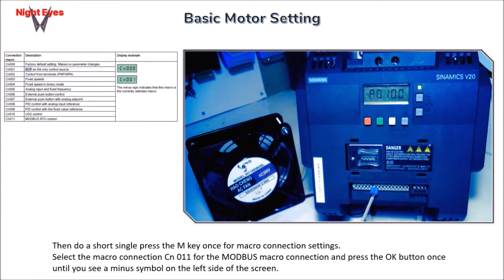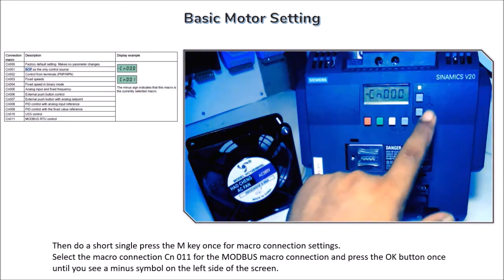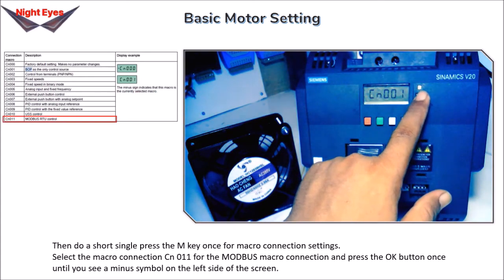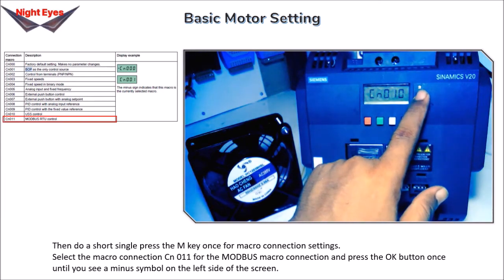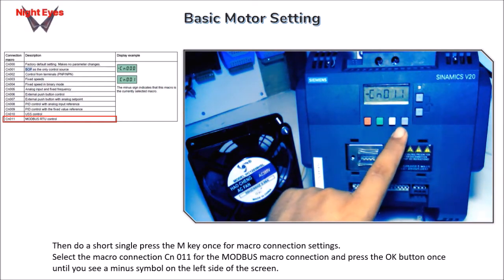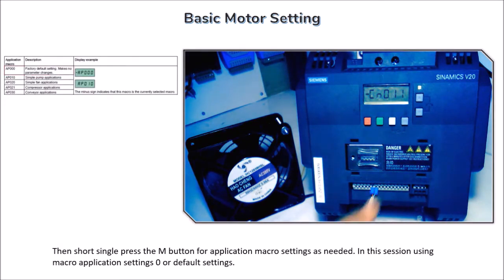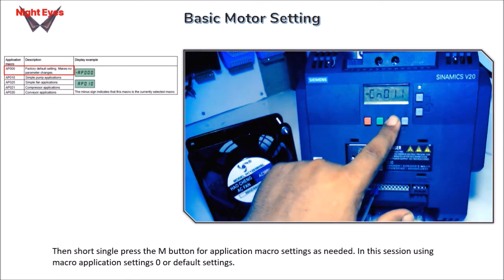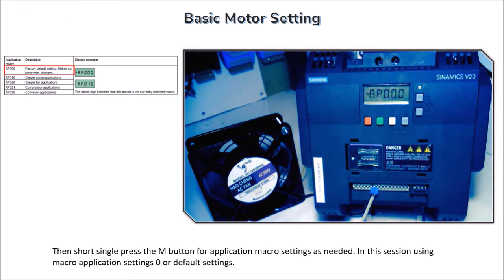Then do a short single press of the M key for macro connection settings. Select the macro connection CN011 for the Modbus macro connection and press OK until you see a minus symbol on the left side of the screen. For application macro settings, this session uses macro application setting 0, the default.